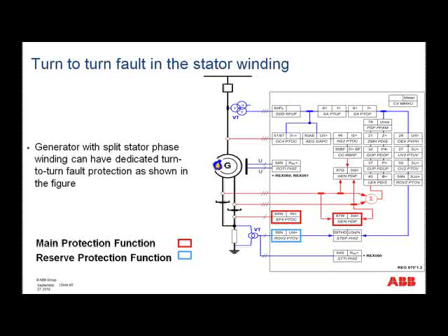these two currents. And then, of course, you could still have your normal 87G, but now from the neutral side of the generator, we would just need to measure both those currents. And then we could sum them, because the other protections are not really interested in how the current is split in the stator, and so the summed value would be fed to the other functions.